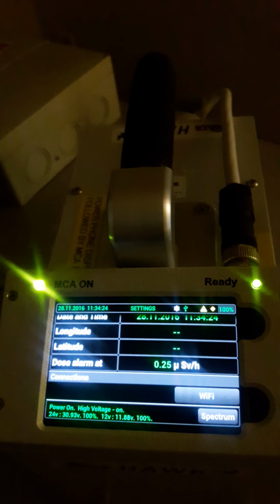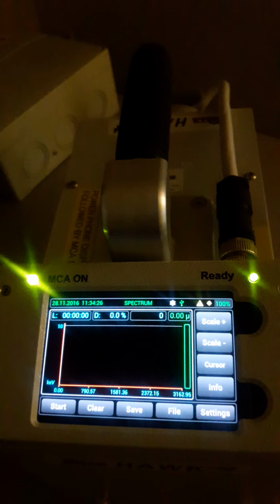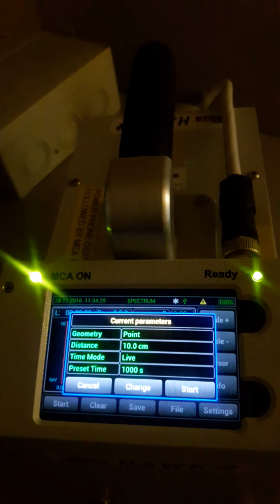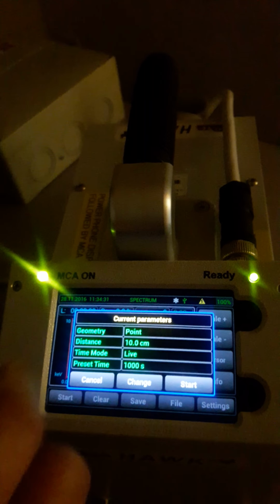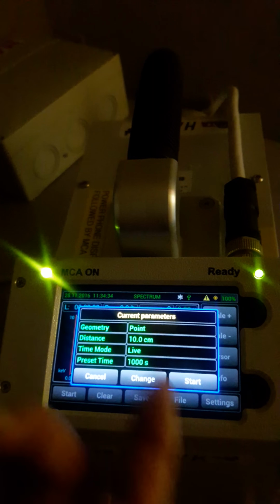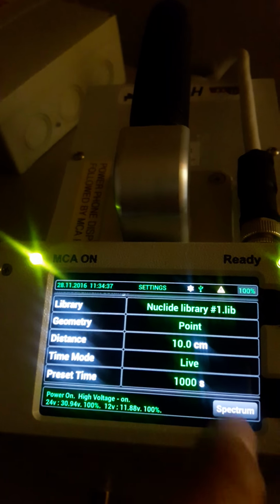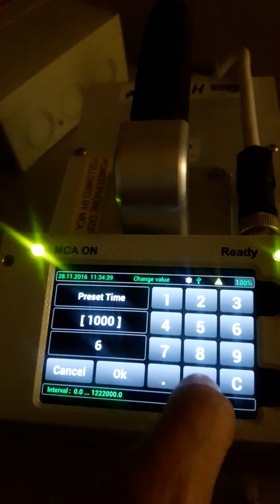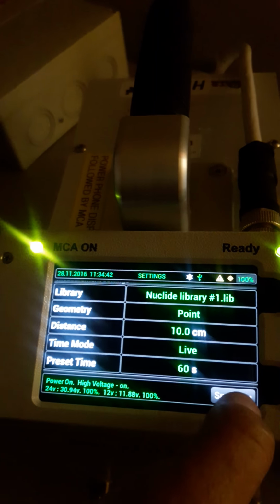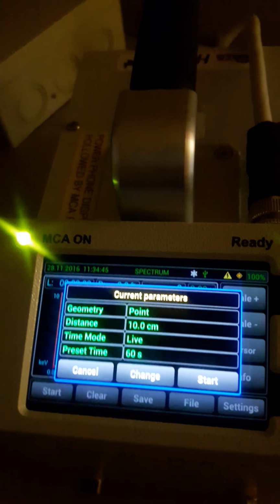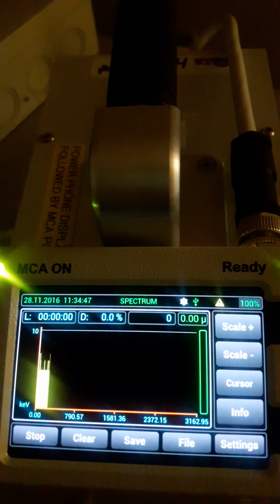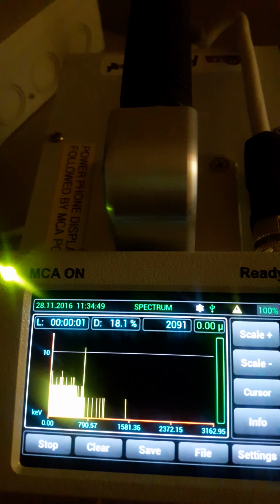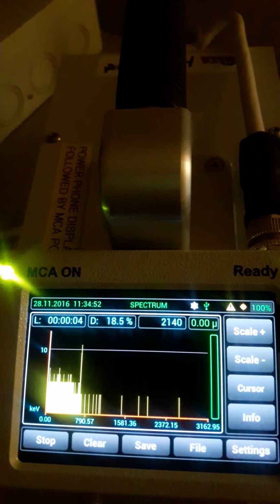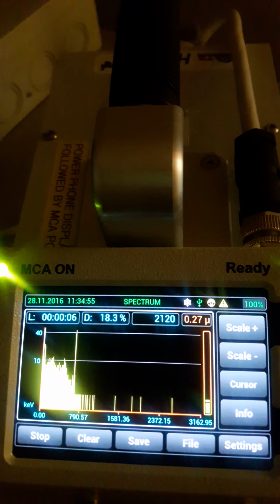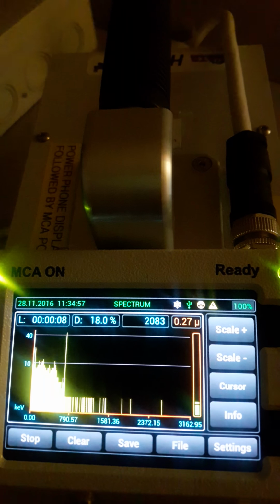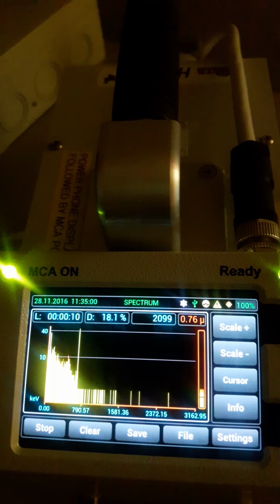I'm going to go back, and I'm going to start a spectrum, and I'm going to try and see if I can see what I have in here. So I'll go back to the spectrum mode. I'll start. This is basically telling you that you're going to count for 1,000 seconds. I'm going to go ahead and change that, and I'll change the count time to 60 seconds just for the sake of this video, and start a spectrum. You should see the screen getting updated. Initially it's not so fast because it's a device that is updating the screen continuously in live time, and you can see that I am beginning to see the cesium peak out there.